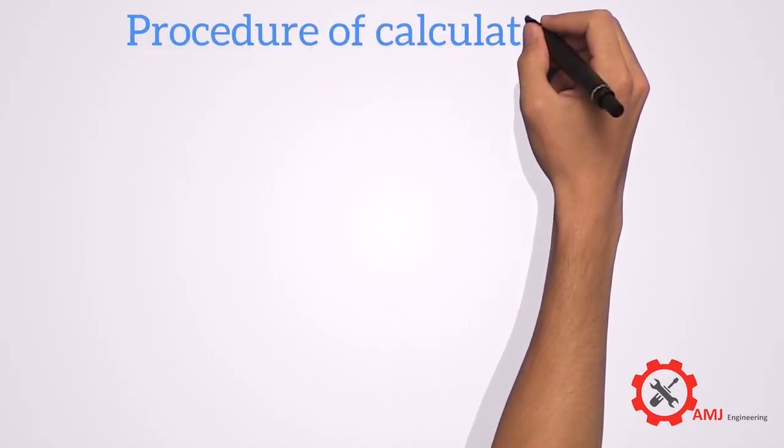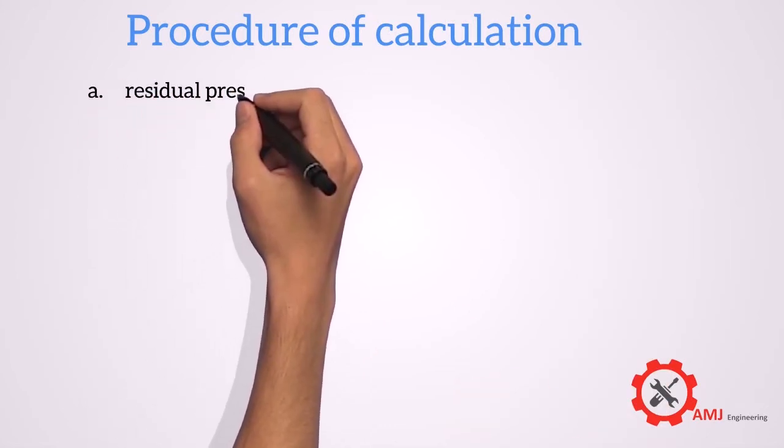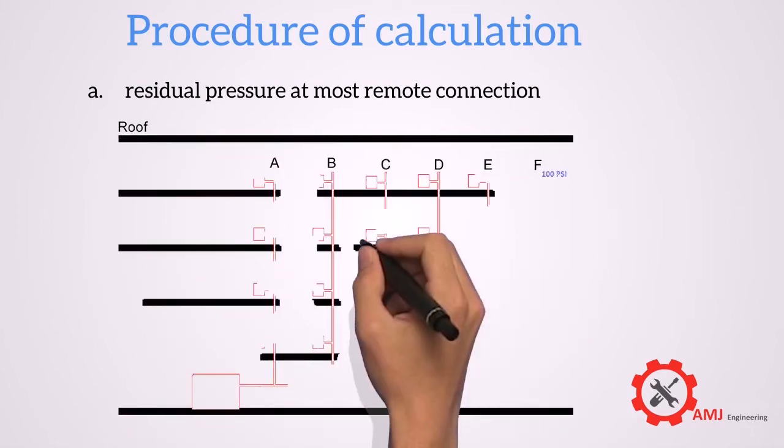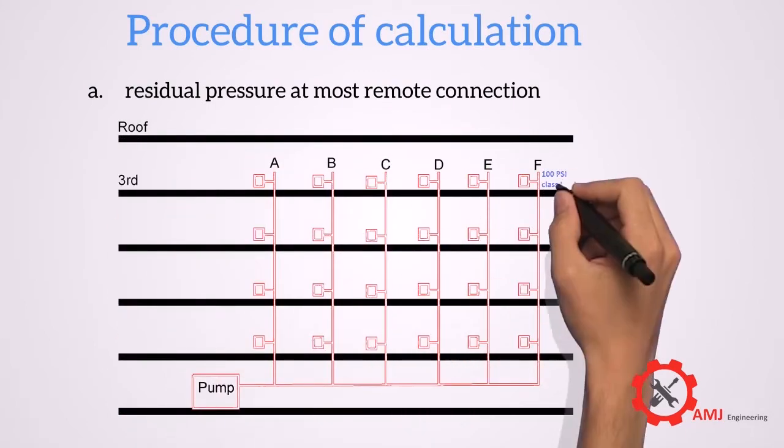Procedure of calculation is as follows. The residual pressure at the outlet of the hydraulically most remote hose connection should be 100 psi for class 1 and 3, and 65 psi for class 2.